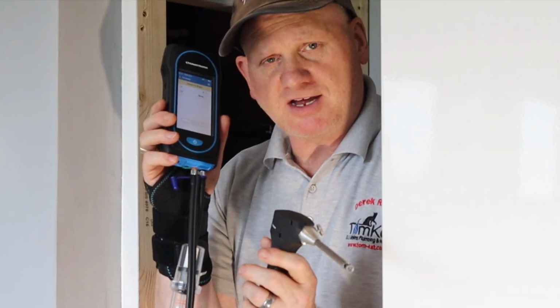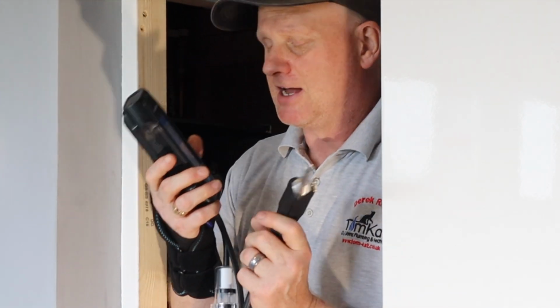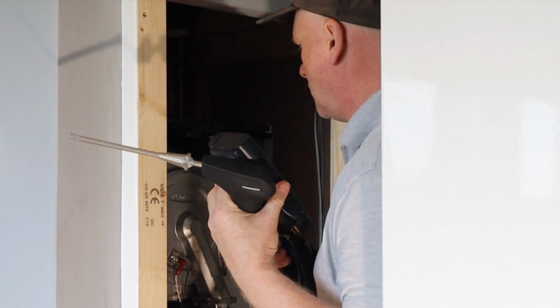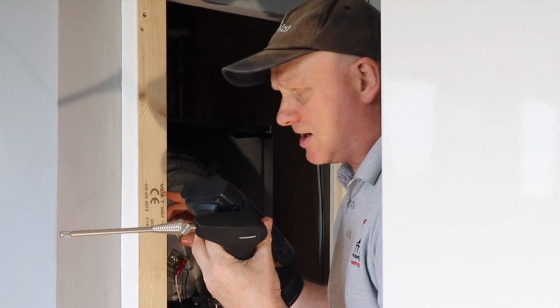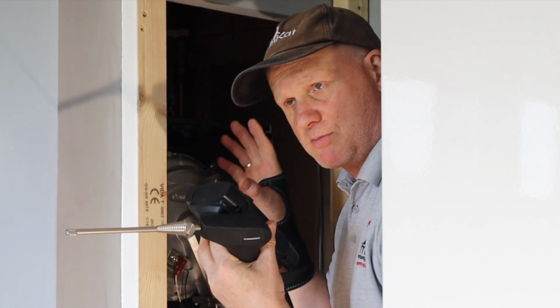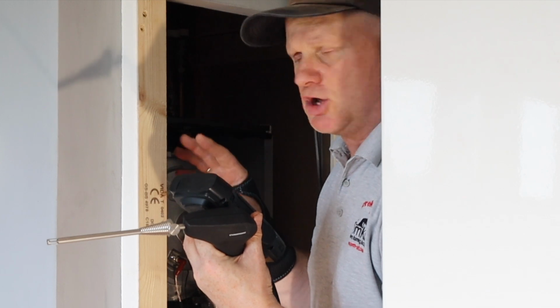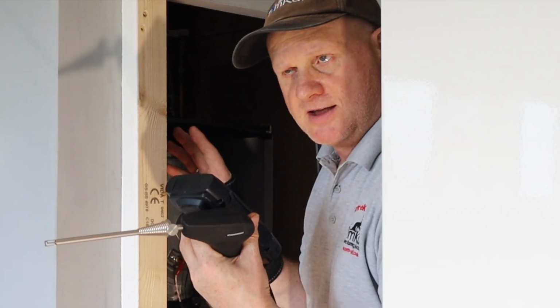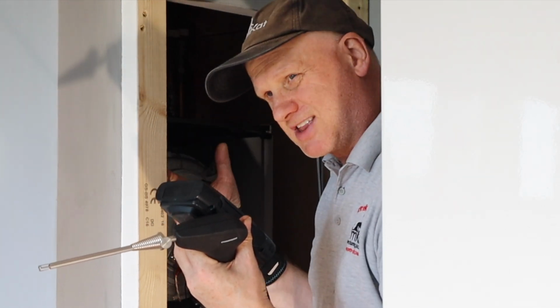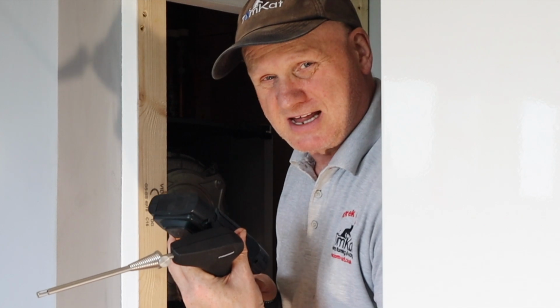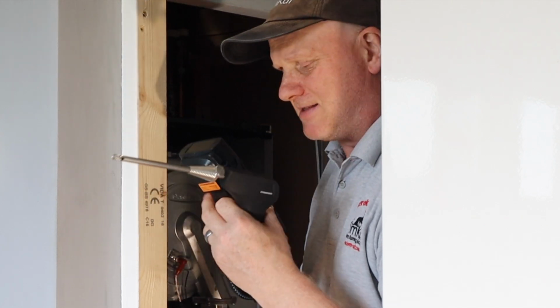I've got my Sauermann Si-CA 130 flue gas analyzer, and the first test I'm going to do is the sweep test around the heat exchanger so that I can put the cover on and then I can do all the tests then with the cover on, so my flue integrity and the actual flue gas analyzer. So let's get on with that then.